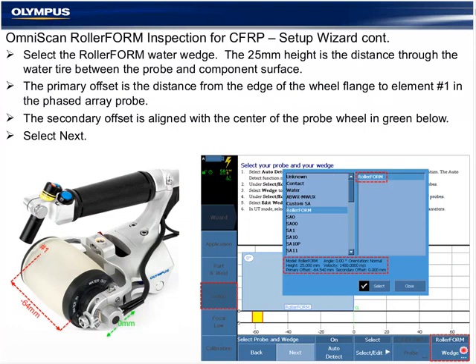Moving on to the probe selection, continuing through the setup wizard, the wedge selection. The wedge or the RollerFORM wheel probe is not automatically detected. It is selected from the database. The wheel in the tire material contains a 25 millimeter standoff in water to put our surface reflection far enough out in time it doesn't interfere with our inspection.